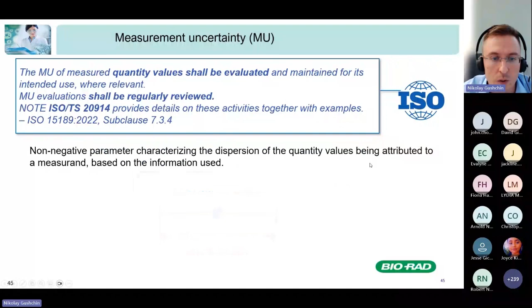Okay. Just a little bit about the measurement uncertainty, to show you how it can be calculated in the software. We have the 3 most used formulas for the expanded uncertainty. The simplest one is SD, just multiply by 2. We also have a formula which takes into account the interlaboratory bias, so we have components for the imprecision and components for the trueness. The third most used formula is the one with the calibration uncertainty. This is the value of the calibration uncertainty, and this information can be taken from the manufacturer insert. Usually they mention the uncertainty of the calibrator, and this information can also be used for the calculations.